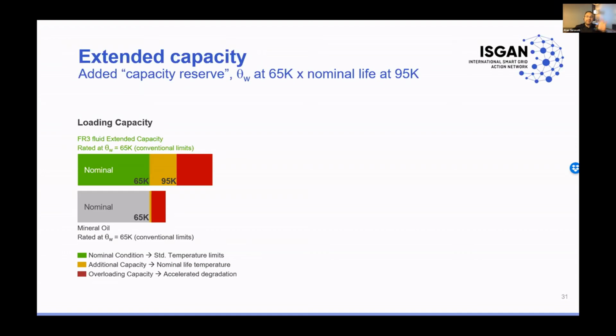Why 30 degrees? Because there are 10 degrees of difference between kraft paper and thermally upgraded, and 20 degrees between thermally upgraded in mineral oil versus thermally upgraded in natural ester. So the effective continuous loading capacity would be when the average winding rise reaches 95 Kelvin instead of 65. So you have 30 degrees more to increase the loading capacity without reducing life. On top of that, you have the red region, which would be the overloading with additional life consumption, which is also larger because the maximum top oil temperature you can have on a natural ester transformer is also much higher than that of mineral oil, 140 instead of 110.